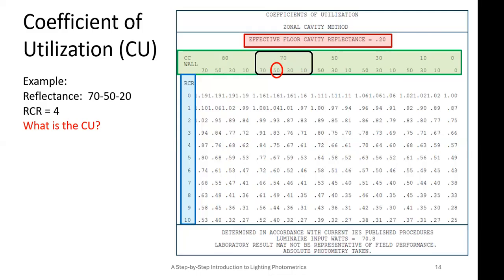So the larger numbers, what that says is all that wall space compared to the floor space eats up light. It just absorbs that light. So therefore, we've got to account for that absorption, and that's what this RCR does with the different values. Okay, so now we've picked our RCR, and we know our example is a 4.